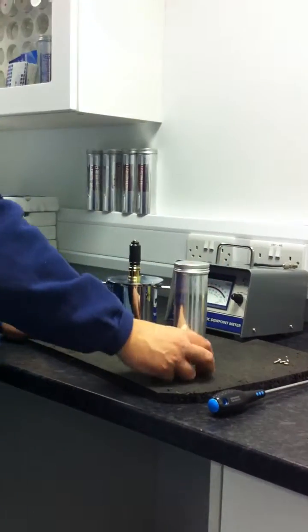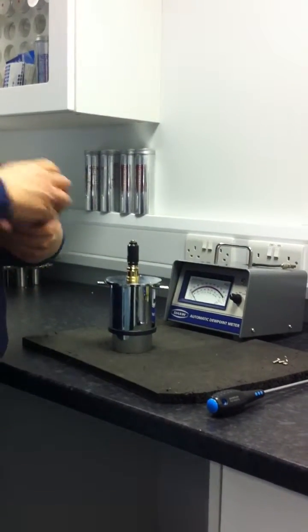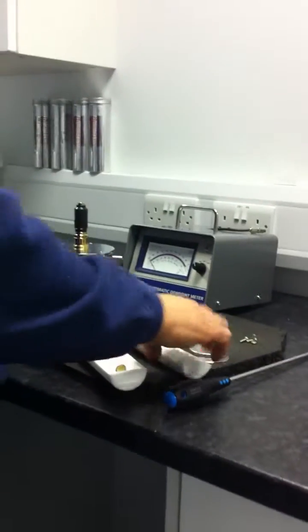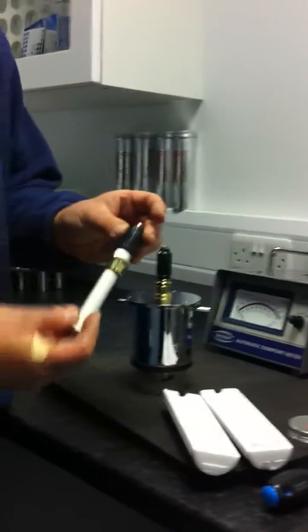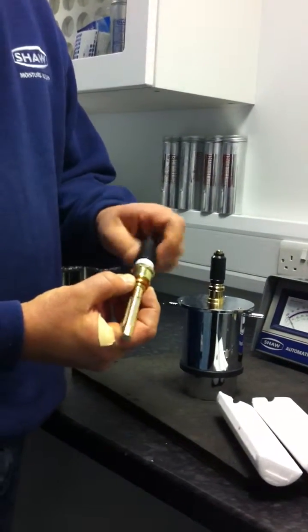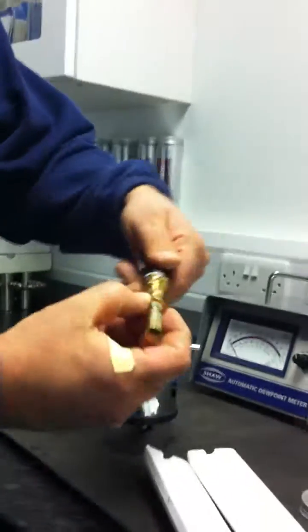Next, take your new sensor that's been delivered and remove it from the sensor packing tin — that's how it will arrive. Take the card protector off; the copper pressure washer is also removed at this point.